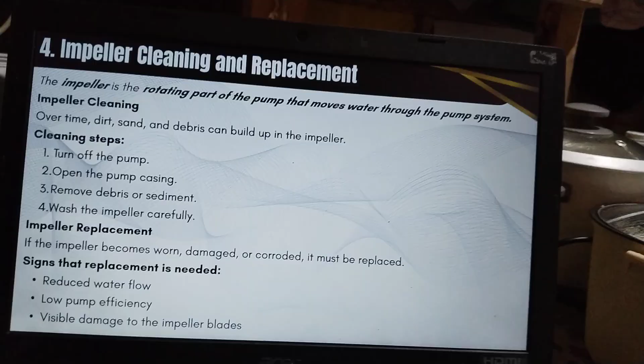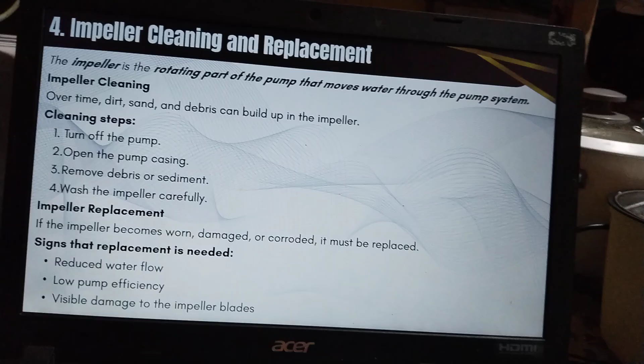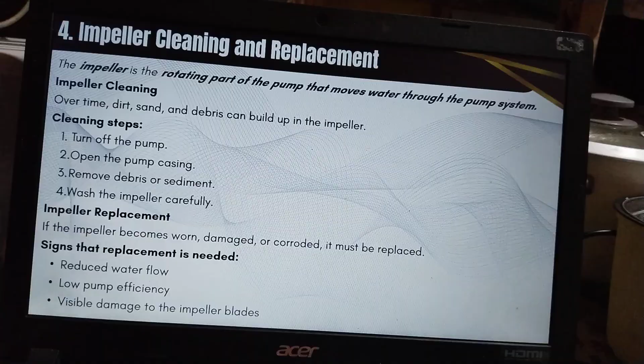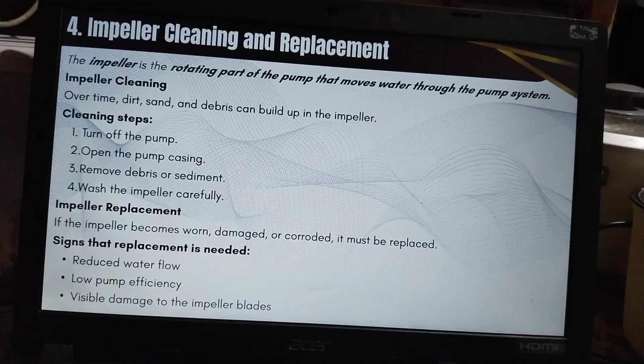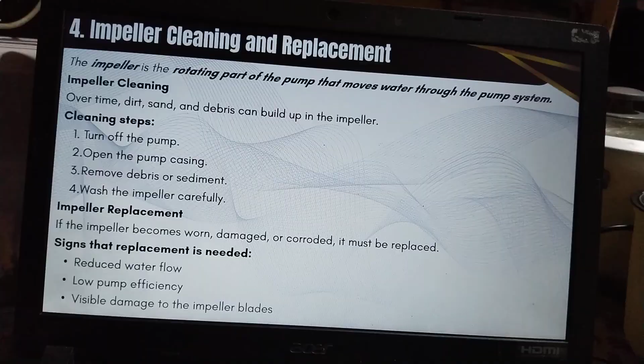Next is impeller cleaning and replacement. The impeller is the rotating part of the pump that moves water through the pump system. Impeller cleaning: over time, dirt, sand, and debris can build up in the impeller. So, cleaning steps: first is turn off the pump. Second is open the pump casing. Third is remove debris or sediment. And the fourth is wash the impeller carefully.